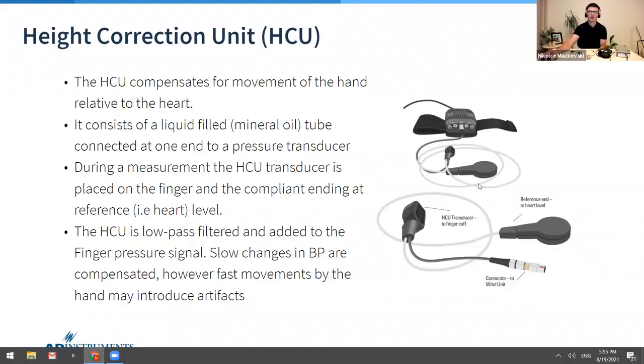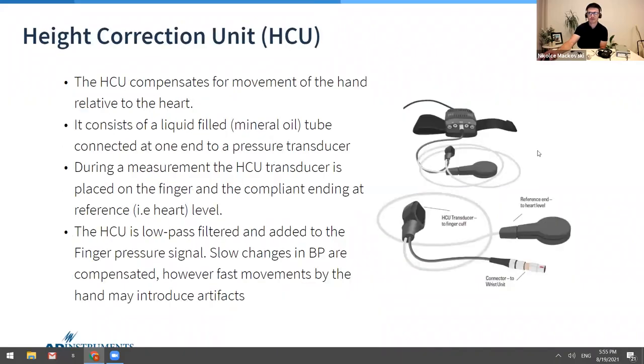This is done by using a line here where one side is the HCU transducer, as you can see, and this would actually connect to the cuff. So if I go back here, you can see that's the HCU transducer that'll connect to the cuff. The other side is a reference end. This reference end is going to be at the same level as my heart level. Within this line, this is a clear tube, and within this clear tubing is mineral oil. Within the reference end, there's also a bladder of mineral oil.